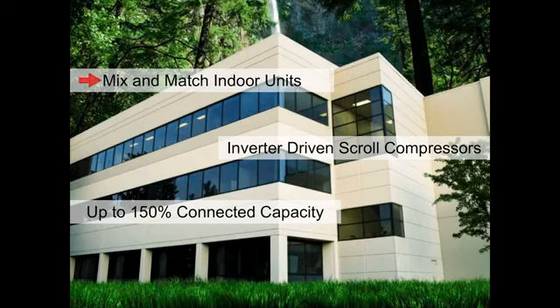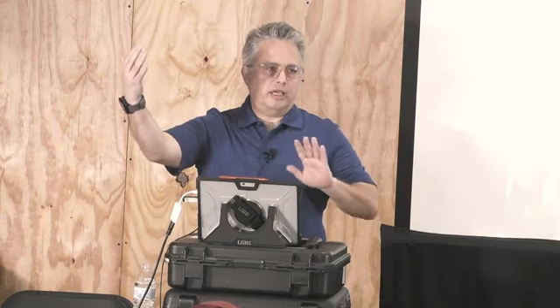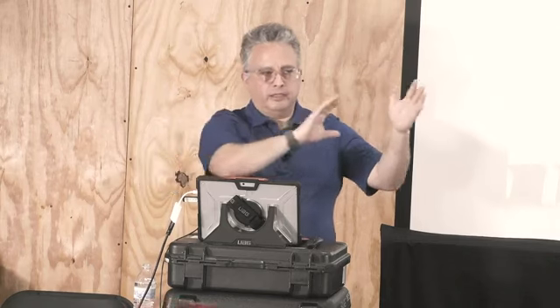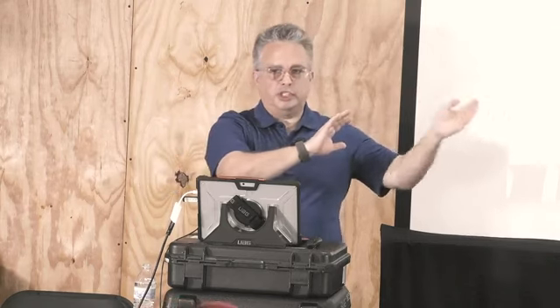You can mix and match indoor units. We're going to go over the different styles that are available for VRF. Inverter-driven scroll compressors. Scroll has been very good to our industry. It's a very robust and reliable way to pump refrigerant. And you can have up to 150% connected capacity. So connected capacity, what that is, let's say you have a 10-ton outdoor unit. You can connect, in this case, at 150%, 15 tons of indoor unit. Now, it doesn't mean you're going to get 15 tons of energy out of it because you only have a 10-ton outdoor unit. The connected capacity of that 15 tons is going to be, that energy will be shared.